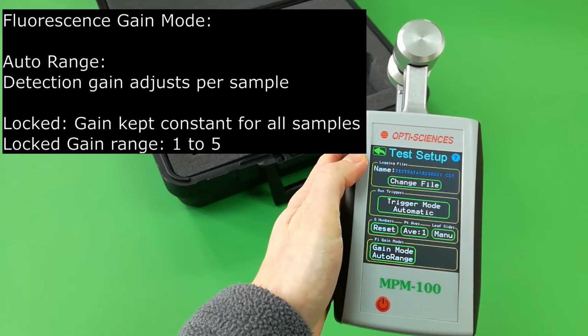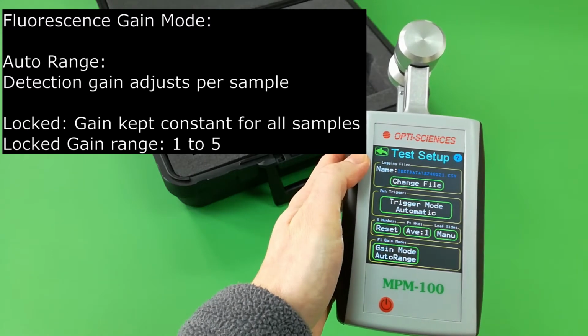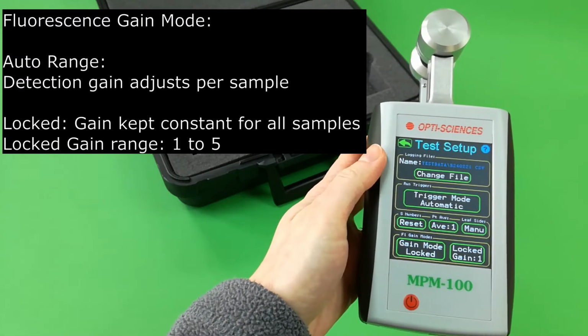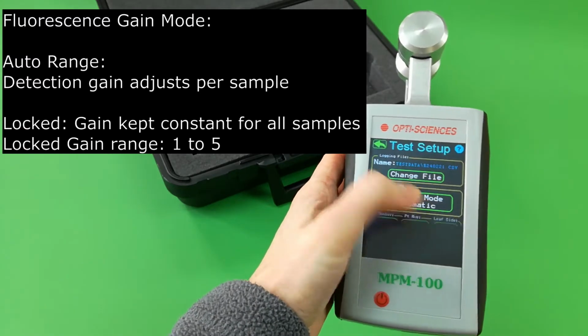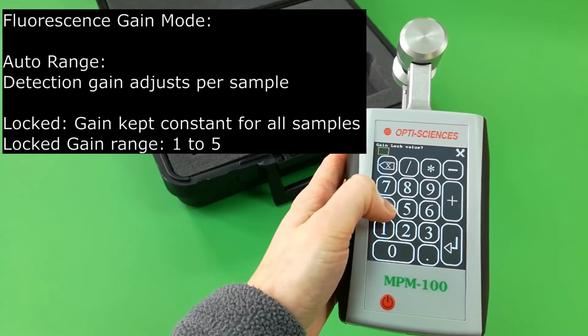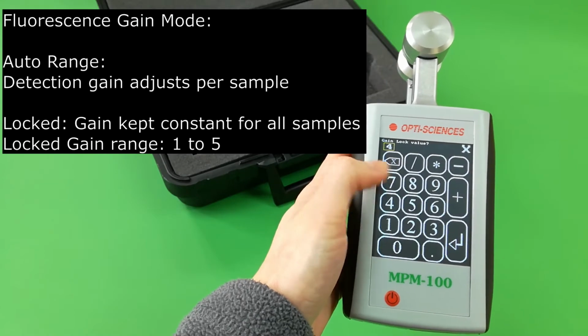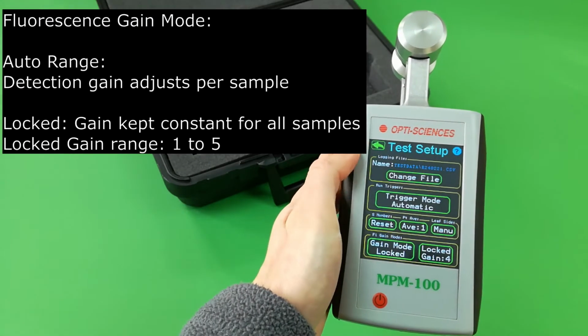Select the fluorescence gain mode, either auto range, whereby detection gain adjusts for each sample, or locked, whereby gain is kept constant at a value of 1 to 5.